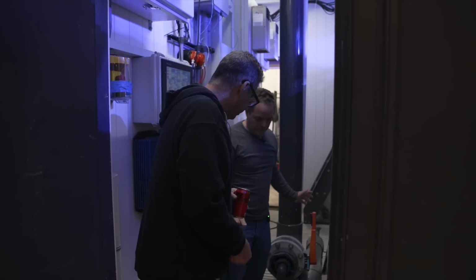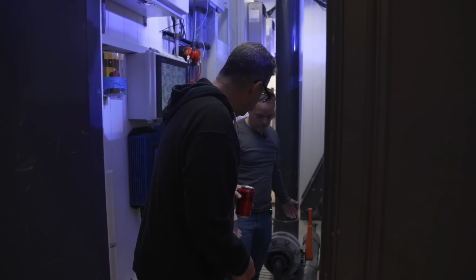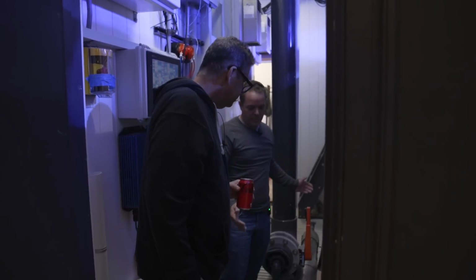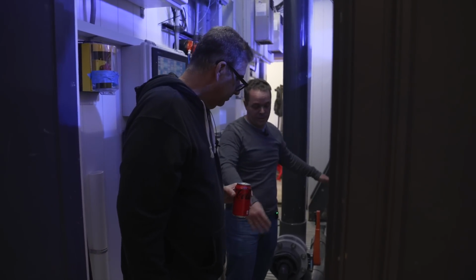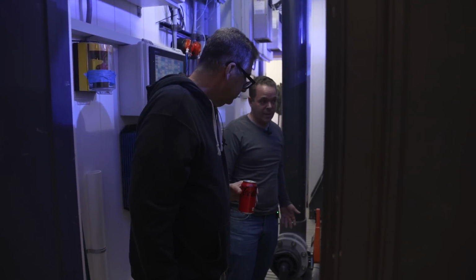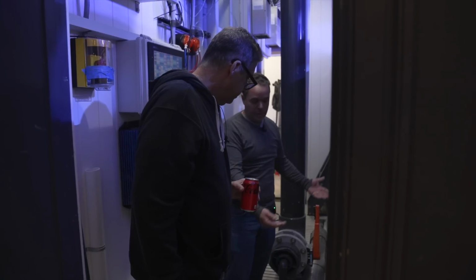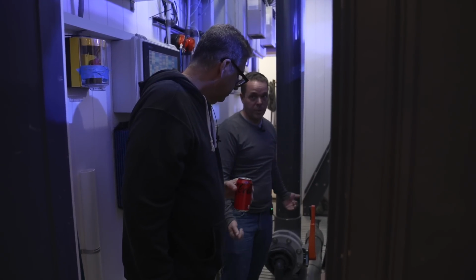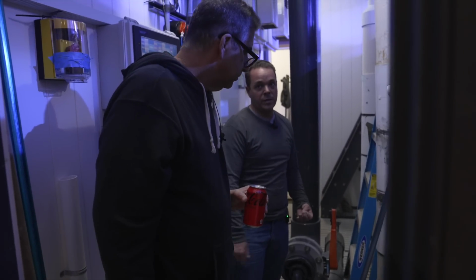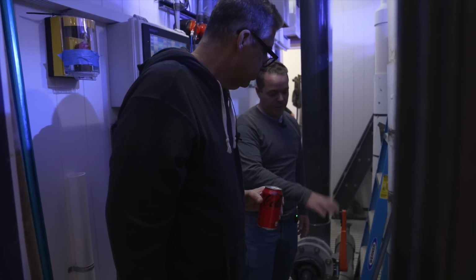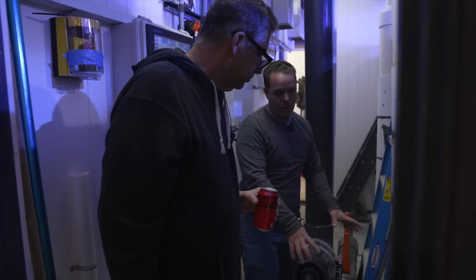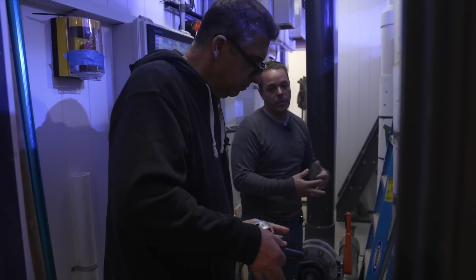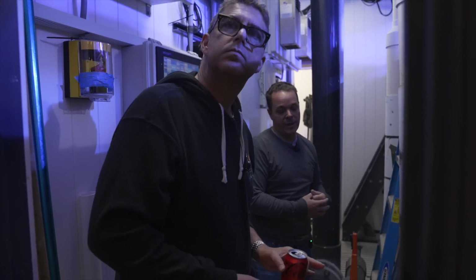Jonathan, let's talk about this beautiful deck you made us. So we're actually, being the tank goes 2 feet below grade, this is actually a hollow pit behind the tank that goes down 2 feet too, where we can connect to the closed loop penetrations that come out the back of the tank. Connect each to a 6-inch header, one being a suction to the pump, and one being the supply to the pump, being the closed loop. And the valves are underneath this floor, where we can just pull up a little section and switch them from supply to return. They're actually 3-way valves.